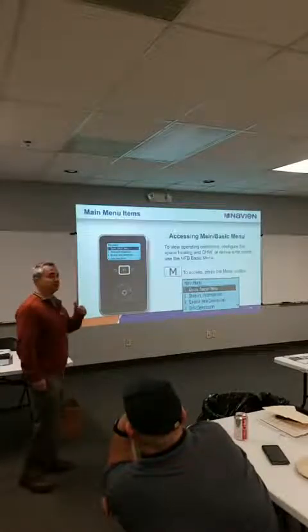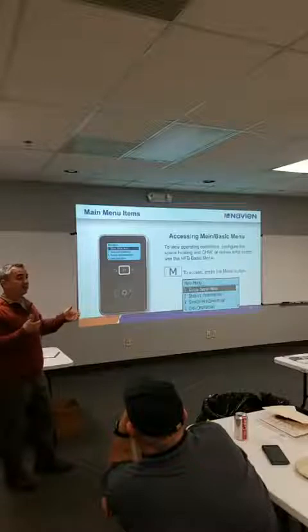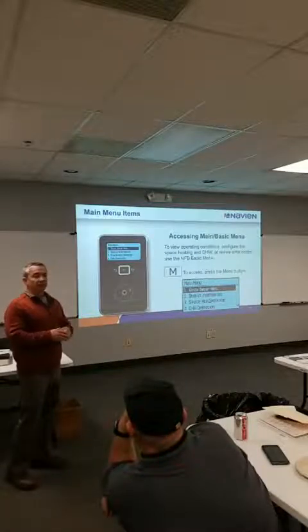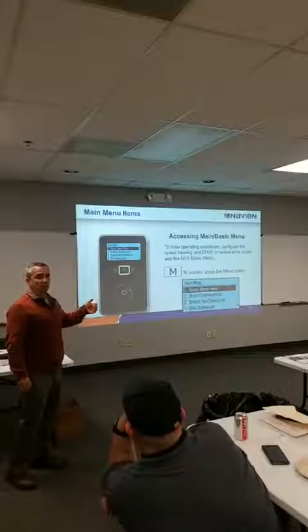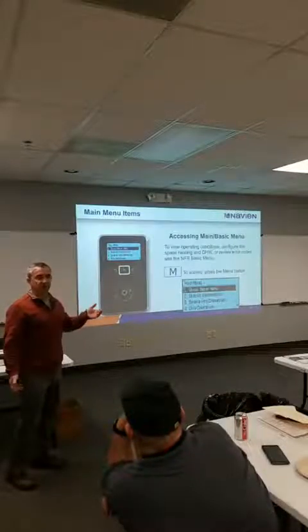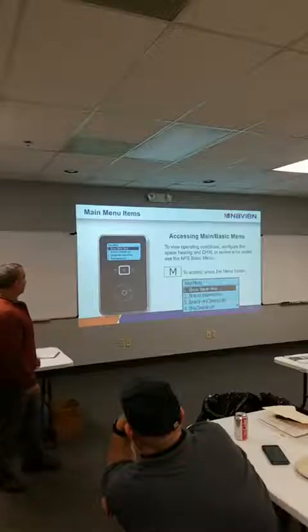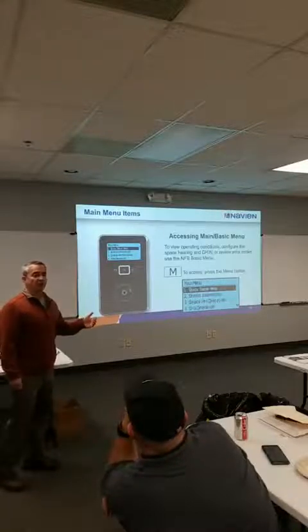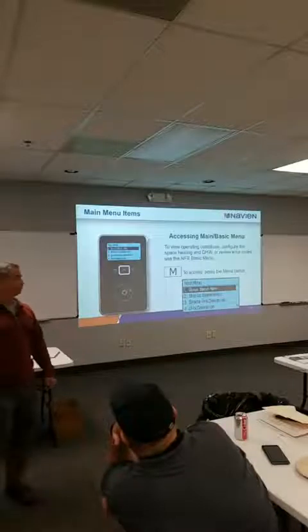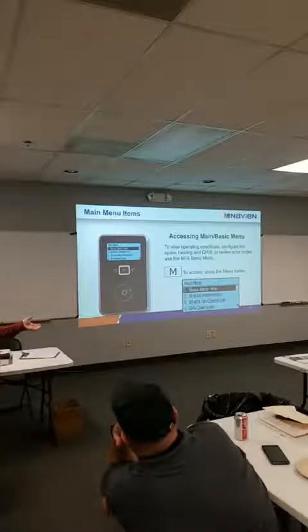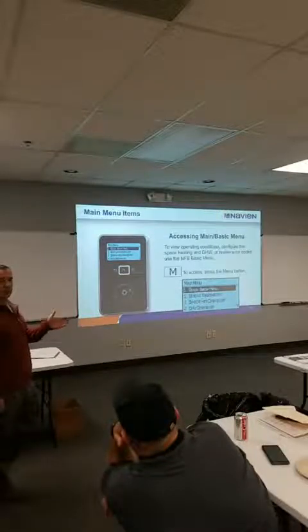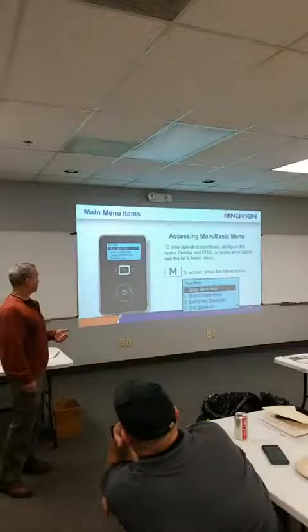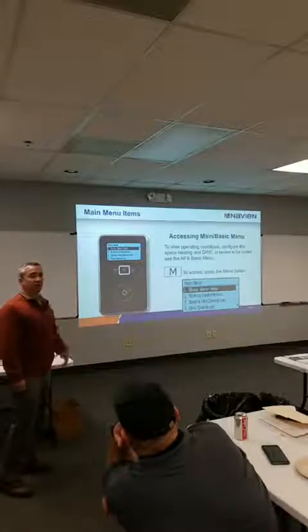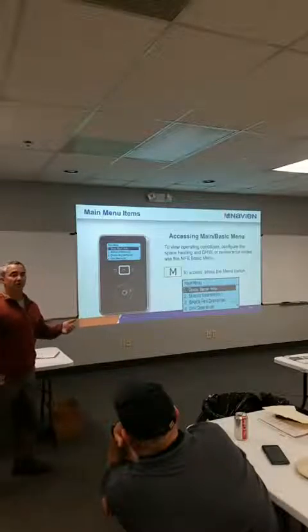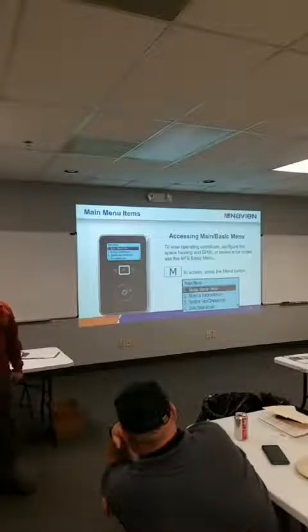Status information tells you exactly what's going on with the boiler. It's like a snapshot as it's running. It'll tell you information on any working component in the boiler and what it's running at. It'll give you voltage, speed on the fan, gas valve, flame rods, temperature, water in, water out, pretty much anything you need to know. For space heating operation, you can go in there and make any changes. All your defaults will be in there. The book will tell you your defaults, or you can go in and make adjustments to them. Same with domestic hot water. You can either run it on default, or you can do a set point and give it priority.